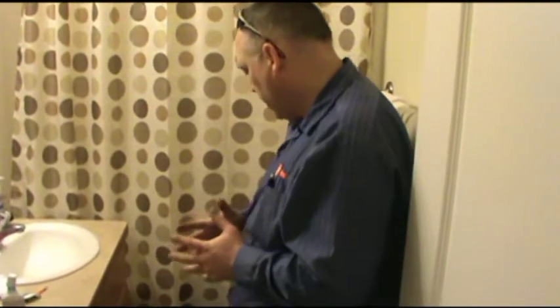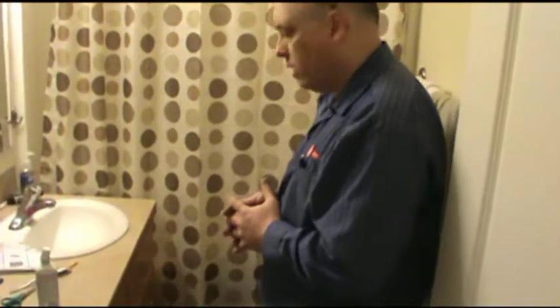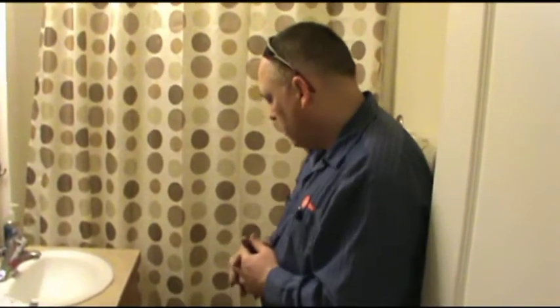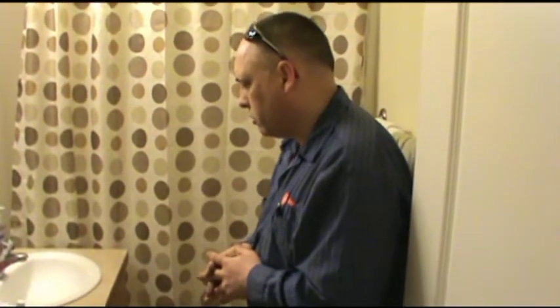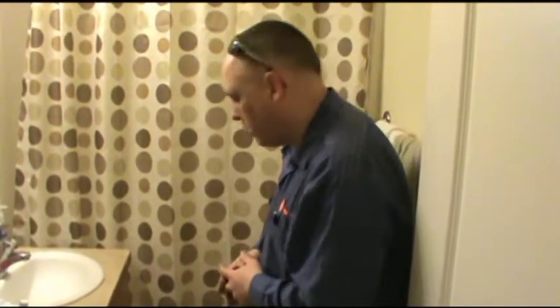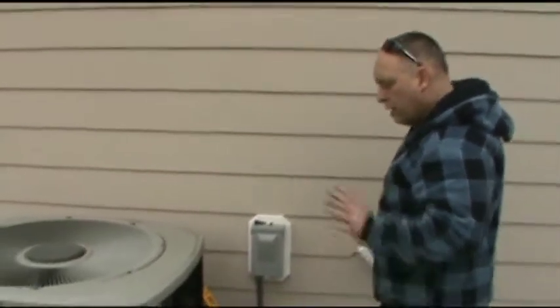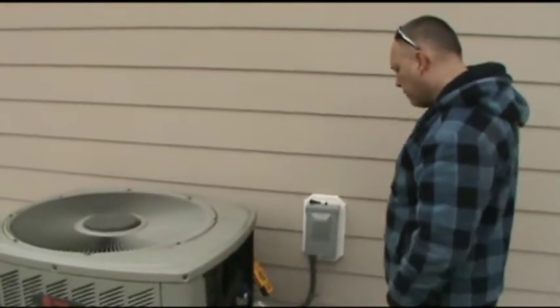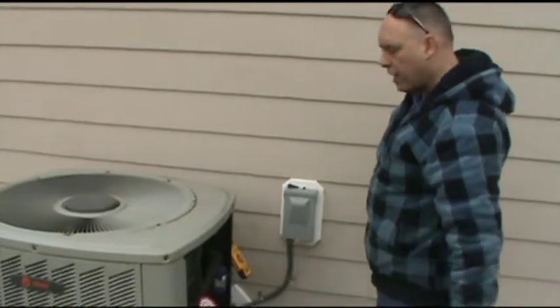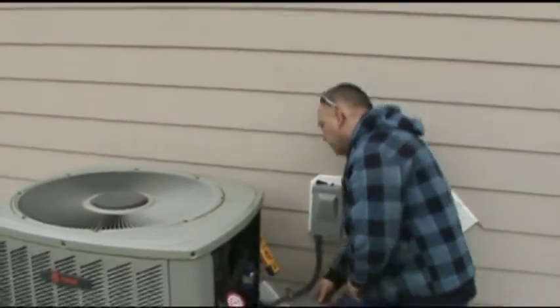The last couple checks we're going to do, we're going to operate the defrost cycle, put it into a test mode, verify that the defrost cycle is functioning correctly. And then even though it's cold out, we're coming into springtime, and I want to make sure the cooling side of the system is working right. So we'll do a defrost check, and then we'll run cooling for just a minute or so to verify that everything is functioning correctly. All right, I'm going to initiate a defrost cycle and verify that it goes through all the steps and processes correctly out here.